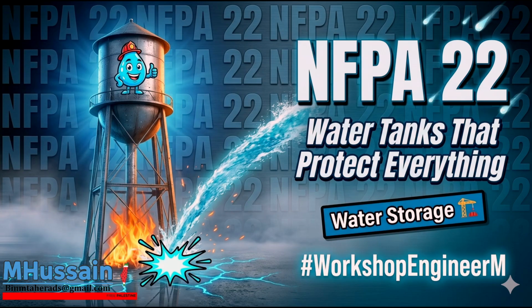Exactly. It physically cannot lift the liquid water any higher. The physics simply break down. If an engineer decides to bury a cistern 20 feet underground to save surface space or avoid frost lines, the bottom 5 feet of that water is forever physically inaccessible to a fire truck. It's phantom capacity. The 15-foot rule ensures the water remains within the strict physical limits of atmospheric drafting. The laws of physics dictate the civil engineering.